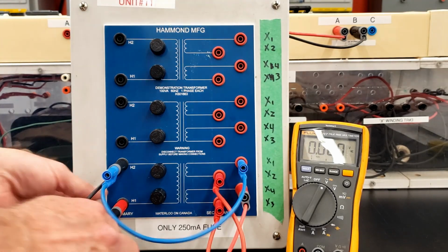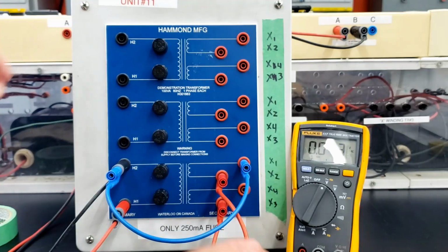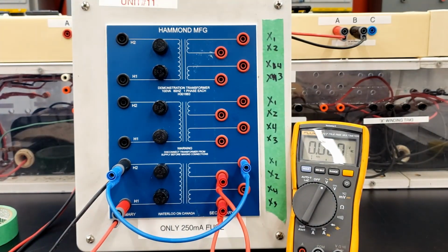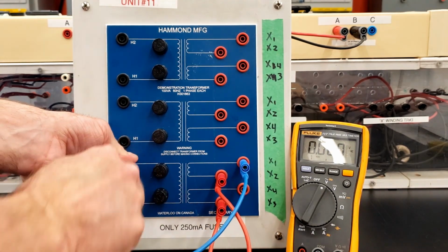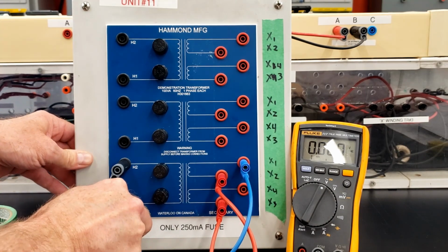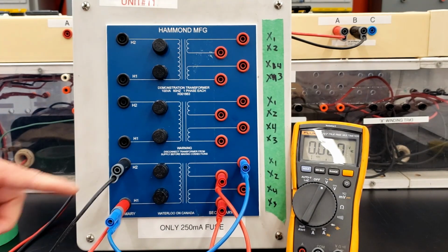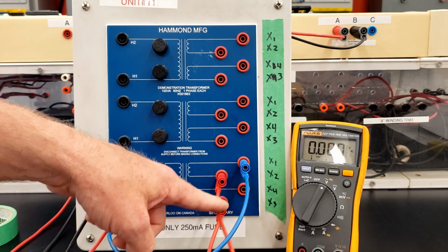We're going to change the connection here. So I'm going to remove the meter leads here. I'm going to change the jumper. The jumper from primary to secondary is the blue conductor. So the blue conductor is now going to go from H1 over to X1, right? So I'm moving this from H2 down to H1, changing the connections between the primary and the secondary.